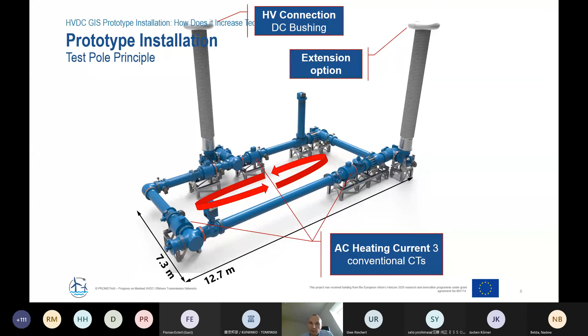Basically, the ring contains the necessary components to construct a typical HVDC substation. We have different shaped elements. We have dismantling units. We have switching devices, disconnector and combined disconnector and earthing switches. We have a fast-acting earthing switch. We can measure DC current and DC voltage with the GIS instrument transformers and RC divider, and the zero flux sensor for the current that is also capable of measuring AC. And we had partition and support insulators. So although we have quite a lot of components, we had 8 compartments because we also used the support insulator. And as an additional solid insulating material, we had also the insulating rod of the disconnector and earthing switches in there during the whole test to also test them for the full voltage.